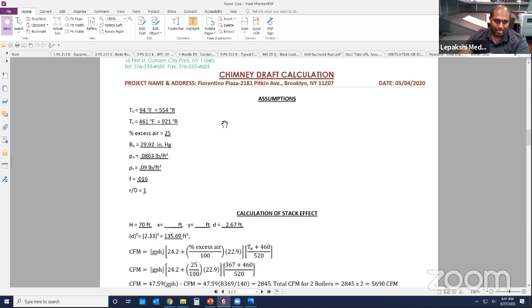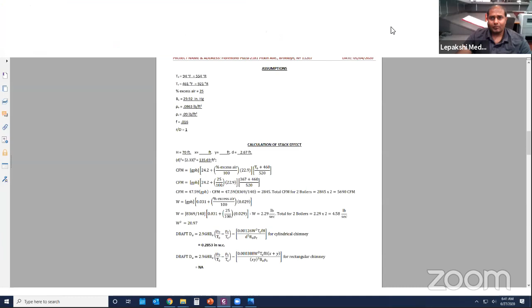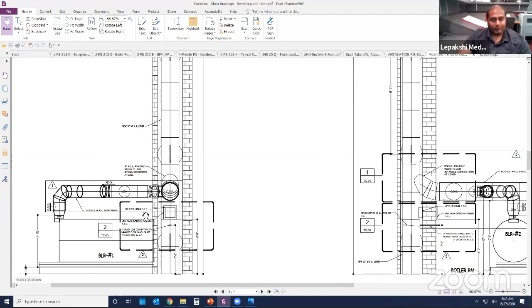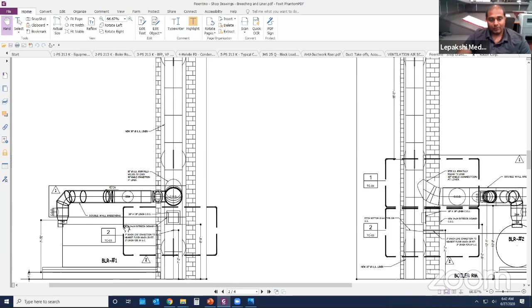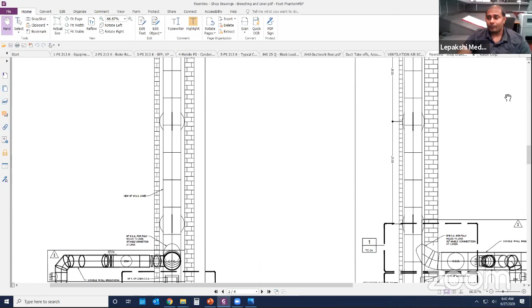So now you calculate how much draft is available. As you know, it's almost 70 feet—why I put 70 feet is, the boiler outlet is already 10 feet above the base. The 80 feet of this chimney is measured from the base of the floor, but 70 feet is from the outlet to the top. So you have to figure it out only from the outlet—70 feet is the usable height of the chimney, I'd say.